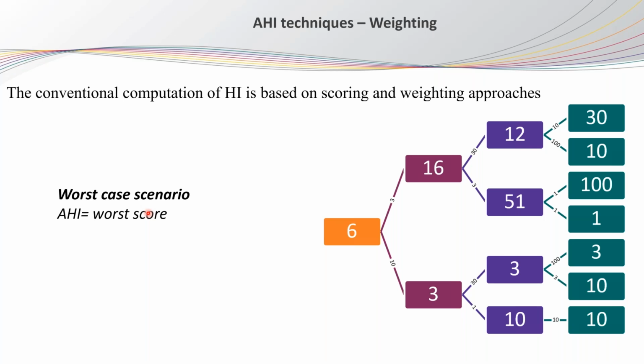The other approach, which is quite famous in the industry, is the weighting approach. With the weighting approach, you give each diagnostic method a weight and give a score to the test results of each diagnostic method. As an example, you have the scores of two test results, 30 and 10. In order to combine them, you have the weight, and this weight shows how important each test is compared to the other. So to combine them, we multiply this value by this value plus this value by this value, and divide by the summation of the weights in order to have one single score for the failure mode.